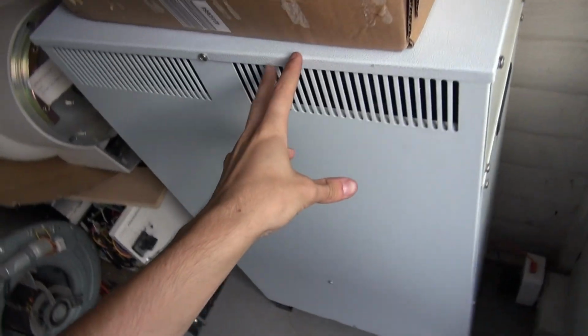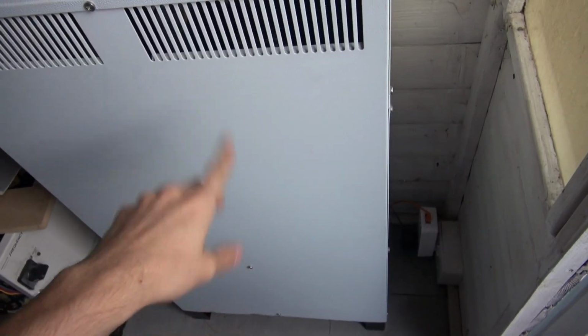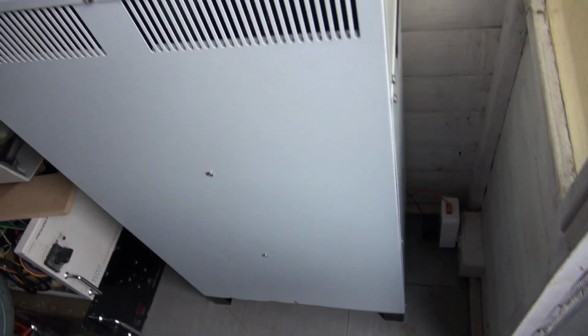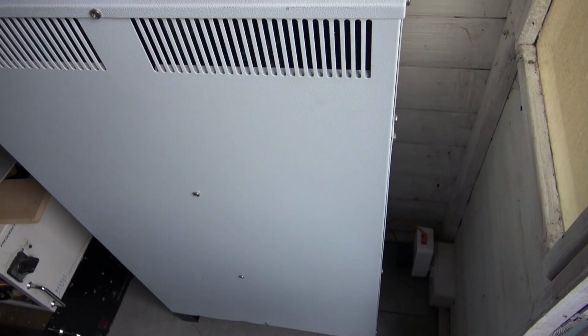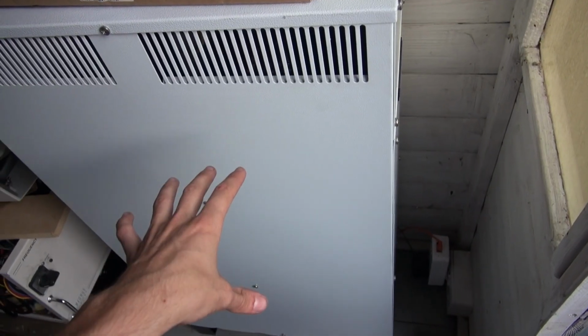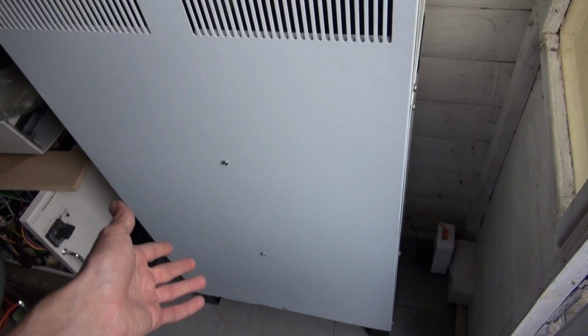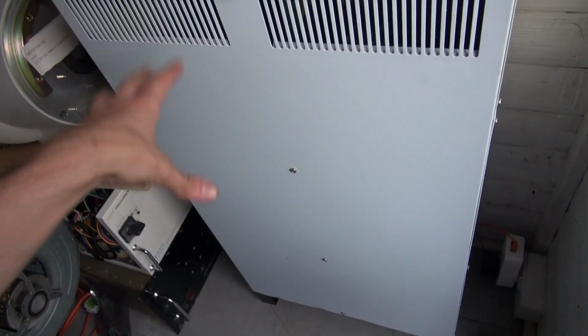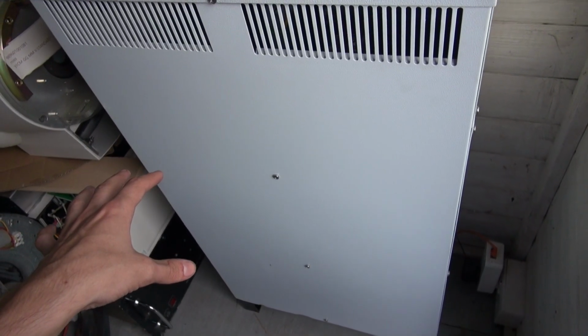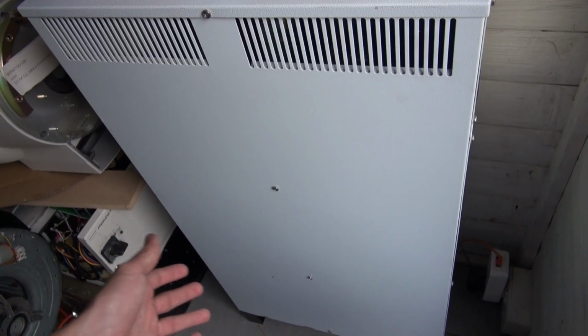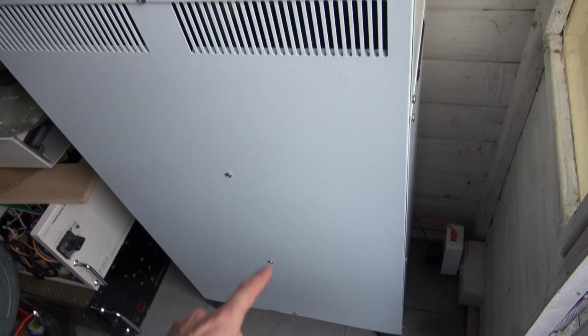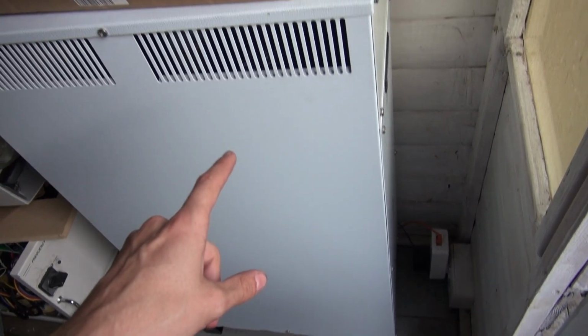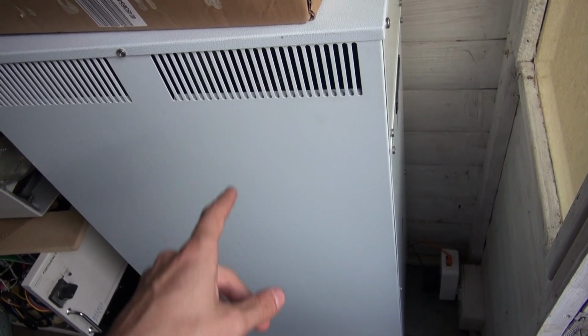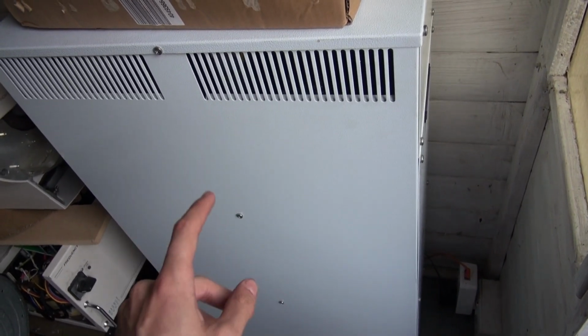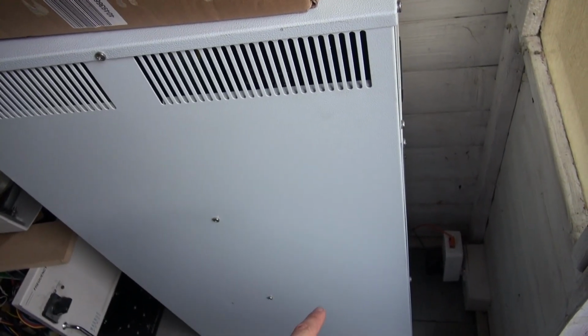Inside, it has three small variacs, 15 amps each, which makes sense given it can do 32 amps a phase. It doesn't just run off the variacs like most TS series units do. The bigger TS series have separate triple-stack or multi-stack variacs to make up a large amount of power. This one has three 15 amp variacs, each with its own control circuit, so each works independently and each phase is independently corrected.